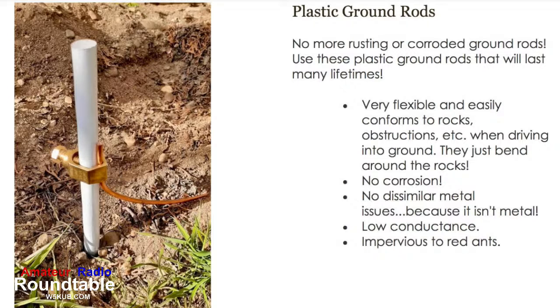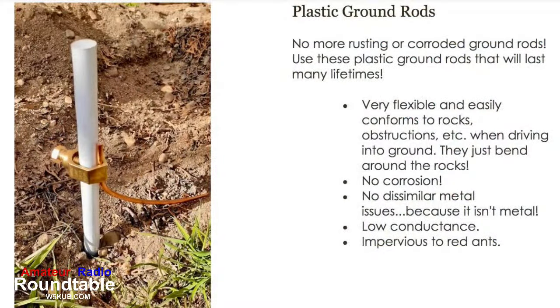Houses today will have, what is it, 2 driven rods, Brett? These days you will have at least 2 driven rods, their lengths apart, on the outside of your house, with a nice thick wire running back to the meter. Now, if you want to clip into that, don't just take your wire and wrap it around it—I've seen people do that. It's not very effective, and it can get corroded. Use a proper pressure connector like this. This is a split bolt, and this will connect 2 thick copper wires together really well. This is what I use when I'm connecting things to the wire on the outside, and I don't have that nice intersystem bonding connector at all, or I'm connecting someplace where it isn't nearby.